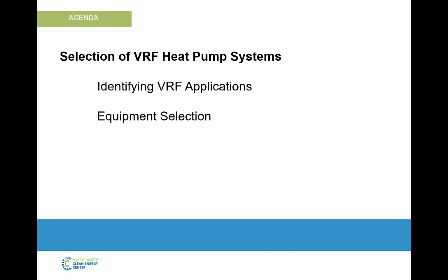So I had a building we did at a university where the facility managers complained: you guys just put in over 200 ceiling cassettes throughout this building, and now we have 200 filters to change and 200 units that we have to watch after. And yes, they did have more filters to clean, and over time they found that changing and cleaning those 200 filters still took less time than the annual maintenance they had to do on the conventional system they would have used otherwise. So there might be more units to touch, but the complexity of what needs to be done is significantly less.